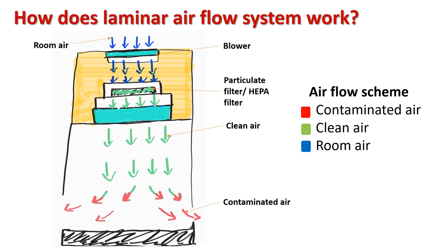How does this laminar airflow system work? When the device is turned on, the blower and the fluorescent light get activated. The blower sucks the room air; large particles are filtered through the filter pad. This filtered air then passes through the particulate filter, which facilitates the removal of micro contaminants such as bacteria or dust. A sterile work environment can thus be achieved within the working area with a uniform flow of air. A UV bulb is also present in the laminar airflow system, which kills remaining bacteria, pathogens, and other micro-level impurities.